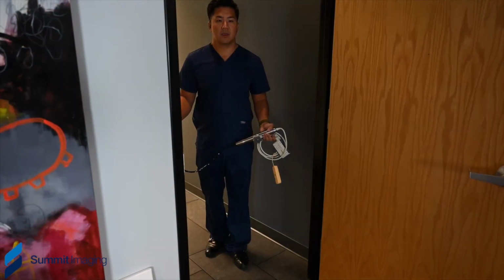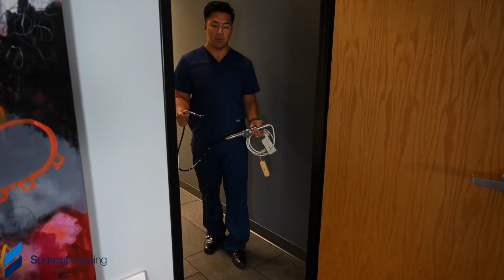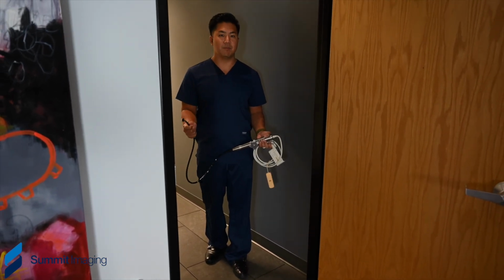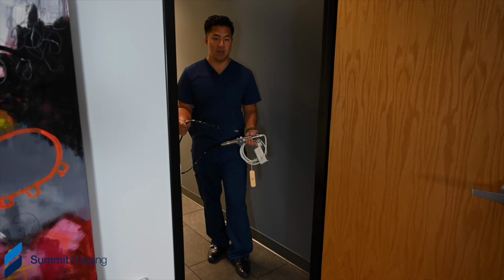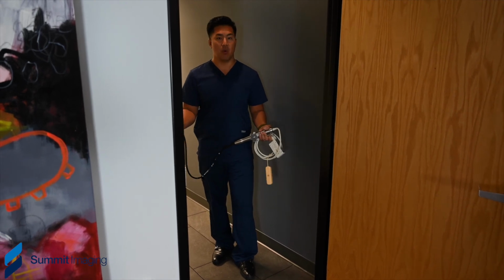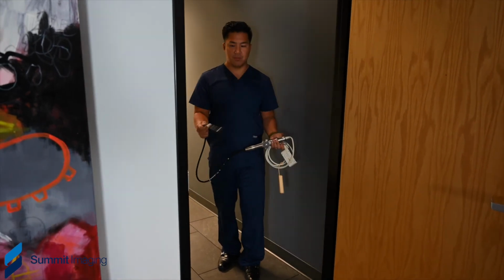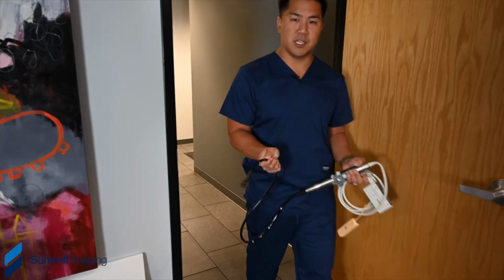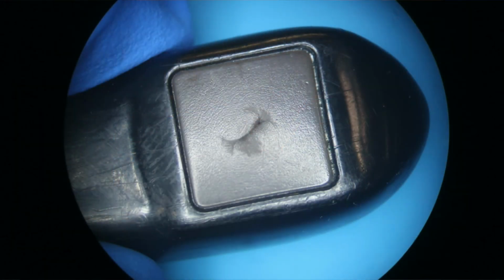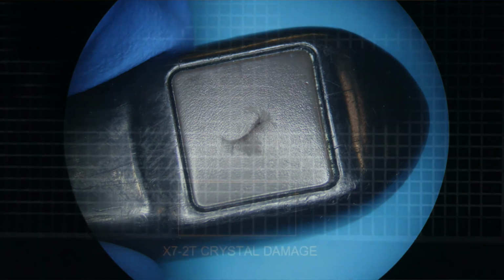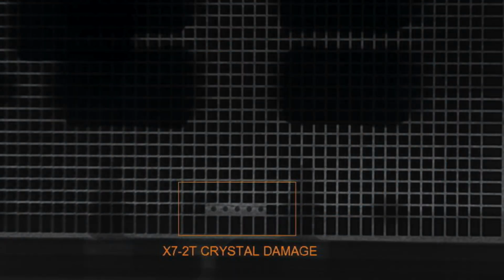So as we're transporting a TEE probe, it's important to protect the tip, because oftentimes accidental damage occurs when just transporting this probe around. And for example here, door jambs are a TEE probe's worst nightmare. Now, that impact on the tip was completely on the tip against a metal door frame, and that will cause enough impact to damage all the microelectronics inside the head of the TEE probe.